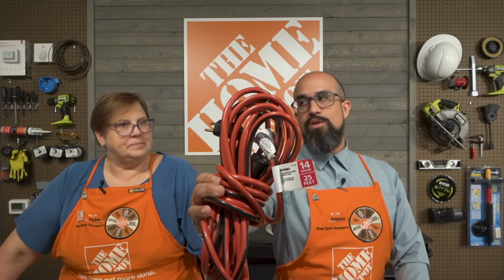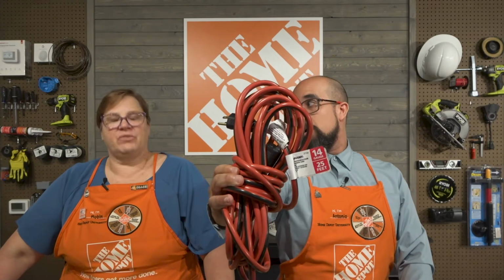Call that out right there - look for that label, 14 gauge. So a 12 gauge would be thicker? Yes, 12 gauge would be thicker, so that would carry more, a little better. So we've got the gauge called out again, and those tools. Another really important area when using these, especially outside, is length - length matters.